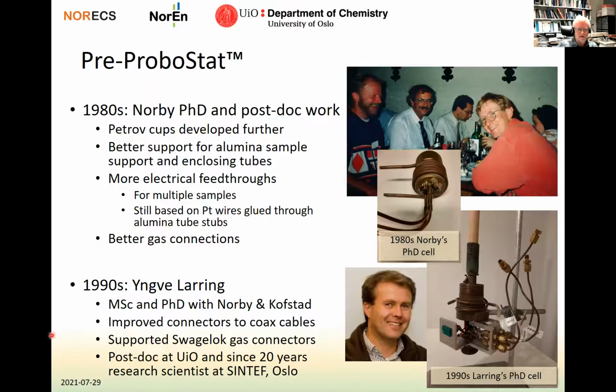We wanted the sample and the electrode contacts to be kept in place by a dynamic spring load, which only has alumina and platinum parts in the hot zone and the springs in the cold zone. And therefore, it can do measurements up to 1600 degrees. It should have a sturdy sample support tube, which is then fastened here with threads instead of the old hole. We wanted 16 feed-throughs and connections for 3 thermocouples, 4 outer and 2 inner electrode connectors, and 4 shields. So there are many feed-throughs.